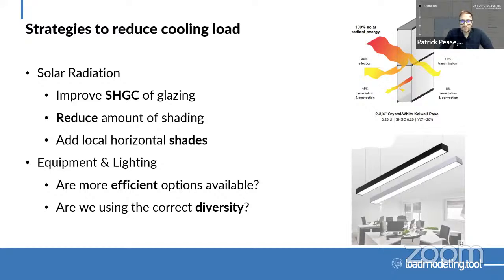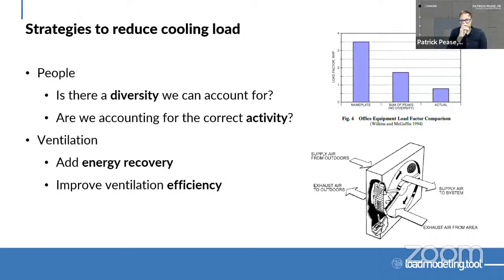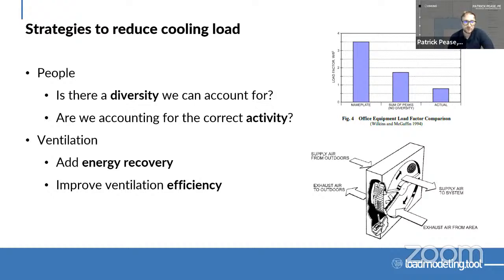Diversity is something engineers can review. We want to make sure we're using the correct diversity in the project. For people, that's really where diversity comes in a lot. If we know there are 500 desks but it's a hot-desking office where not everyone is in every single day, we can use a higher diversity factor. For conference rooms, we can definitely increase diversity. Making sure we're not oversizing by looking at the whole picture, not just the specifics of each room, is helpful.